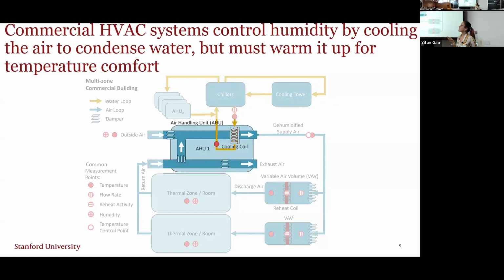Most of the magic happens in what's called an air handling unit, or AHU. Water from the chillers goes into cooling coils, and air flows over the coils, cooling the air down. If the air is really humid, this is where the temperature drops and the water condenses.